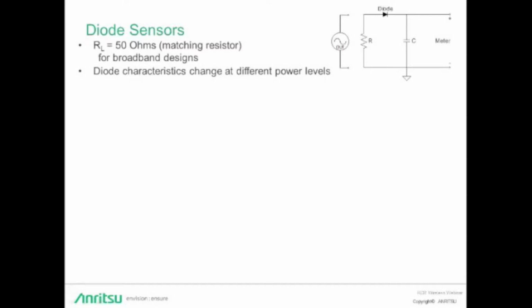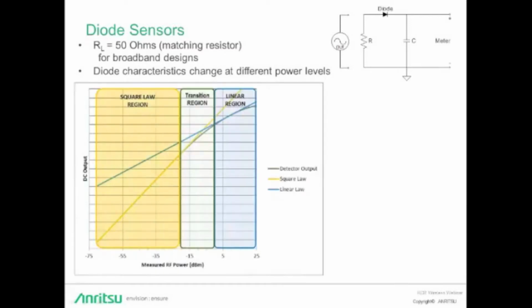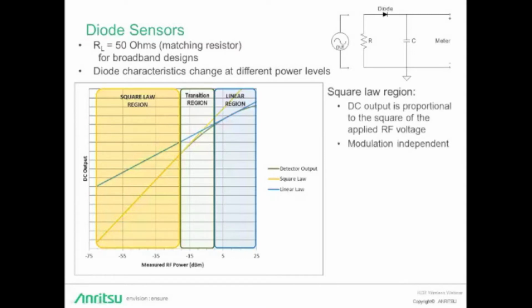So diode behavior can commonly be broken down into three regions of operation. Below -20 dBm, diodes produce a DC output that's pretty closely proportional to the square of the applied voltage. This is what we call the square law region of the diode sensor. In this region, the average DC output voltage is going to be proportional to the average RF power. So even if modulation is present, as long as the peak power remains in the square law region, this sensor can measure the average power of any signal type. In other words, it's modulation independent. Just be cautious of signals with high peak to average ratios or crest factors. Be sure that the peak power remains in the square law region of the diodes at all times.